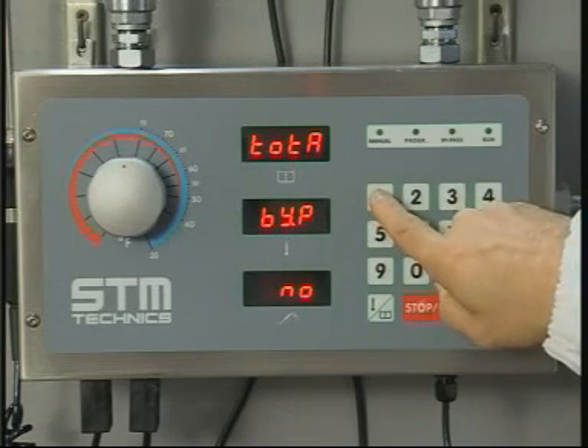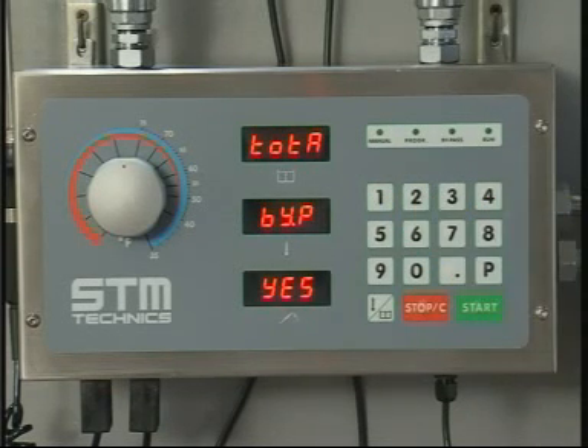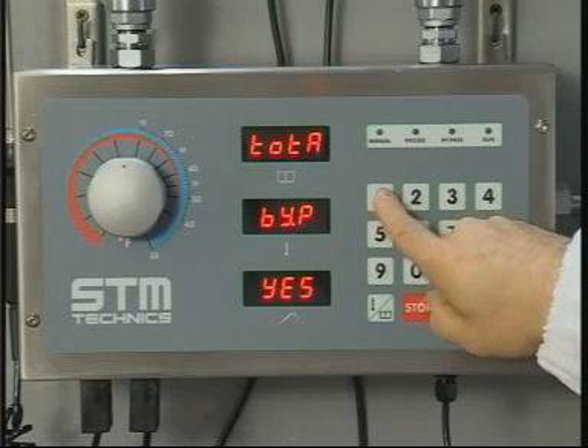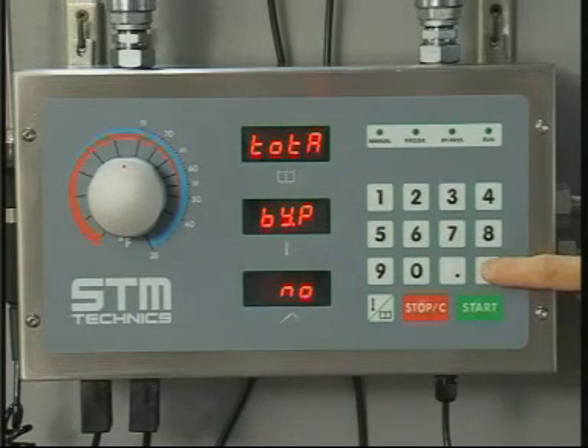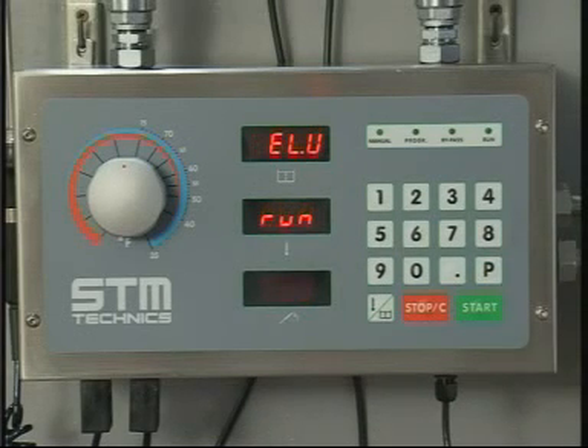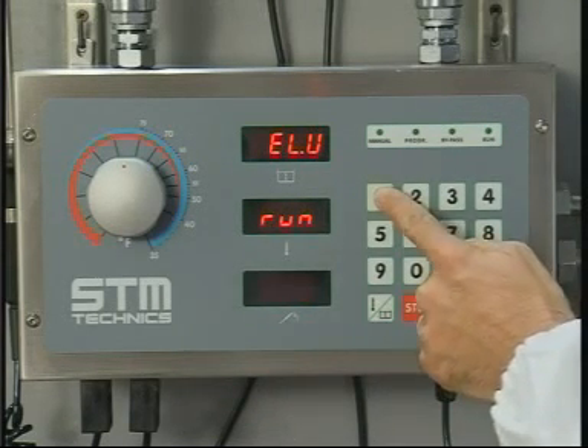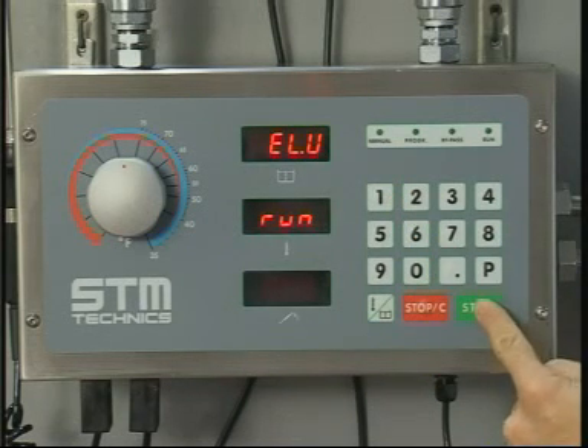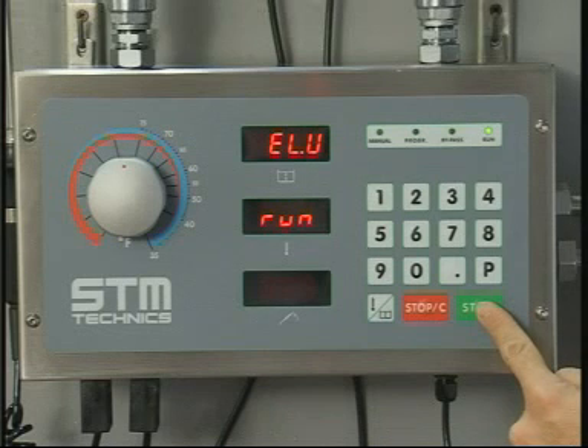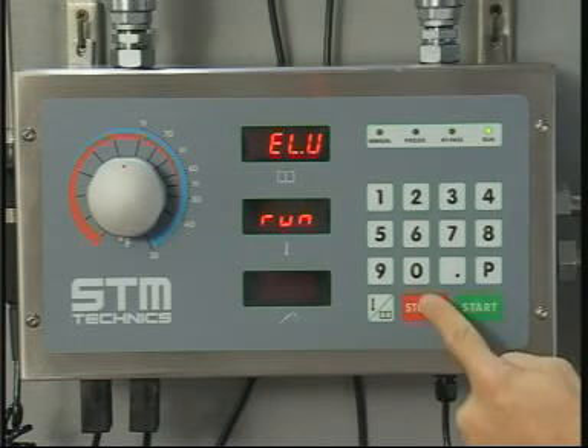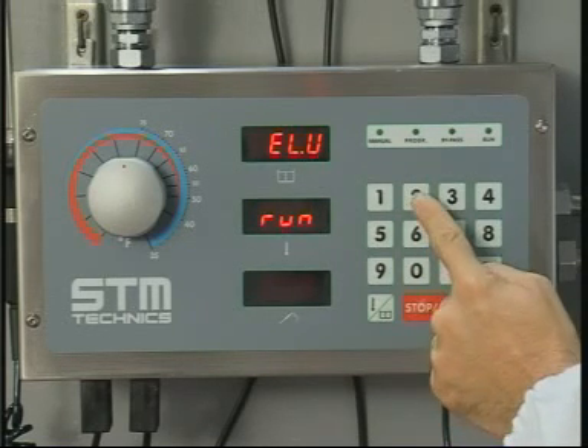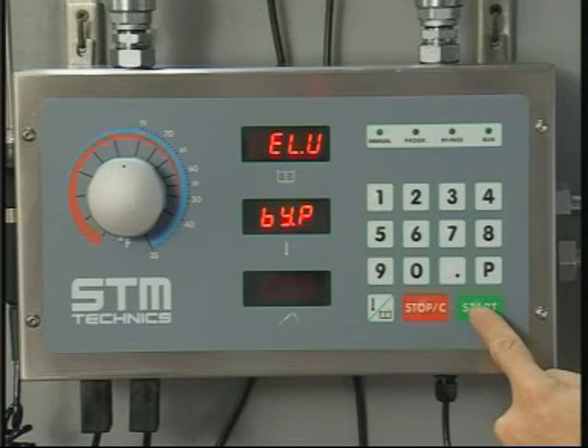Counter of used water expressed in cubic meters. If yes is chosen in this display, the counter will keep count also of the water discharged to the bypass. If instead no is chosen, it will keep count only of the water discharged to the mixer. ELV run. In this display, it is possible to check independently the main electro valve and the bypass electro valve with keys 1 and 2. Choose the desired valve and by pressing start it opens. Pushing stop it closes.